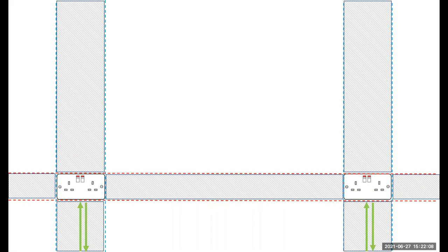Okay, here is a basic diagram showing how you could run between two points in the wiring, either horizontally or vertically. So what I've done here is I've marked the zones, the prescribed zones. Obviously, the easiest, quickest and safest way to comply with the regulations is to take the shortest route. And if the sockets are low level, then it would be from the floor upwards. This makes it really easy to use up the rest of this space for decorations, mirrors, furniture, etc.